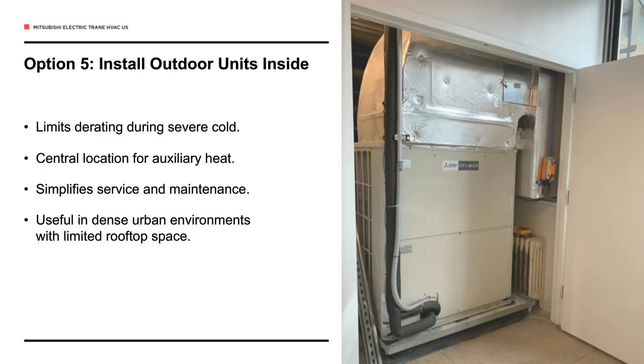Option number 5, we can take the outdoor units and install them inside the building. This was somewhat popular early on when VRF was brought to the United States in the early 2000s in the extremely cold states like Wisconsin and Minnesota and North Dakota. You take an air-cooled unit, put it in a mechanical room, and then I'll show you on the next screen what that looks like schematically. But essentially, not only are we getting the equipment out of the weather, so it's easier to work on, it's not being snowed on and rained on and hailed on, but we're turning the mechanical room into either a mixing plenum or a recirculation air plenum or a pass-through air plenum, depending on the outside temperatures. So I think the next screen will show what I'm referring to.